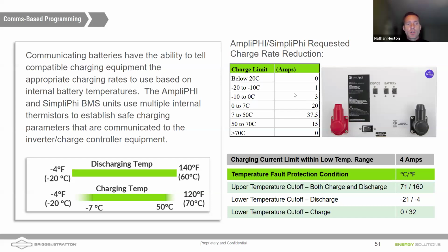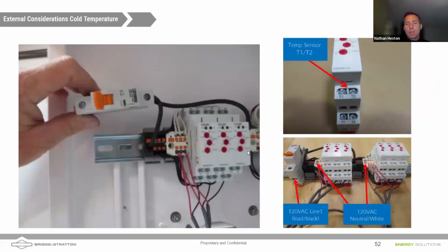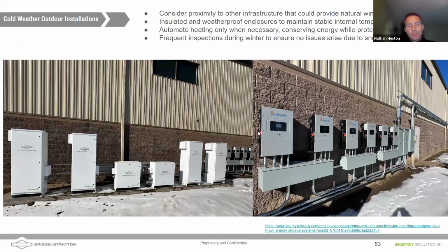So this battery will charge all the way down to -4 Fahrenheit. So it's quite a low temperature. And again, we can integrate heaters. So here's an example of a heating system that's being integrated in, and those heaters go directly on the batteries themselves, which is more efficient than heating an overall cabinet.